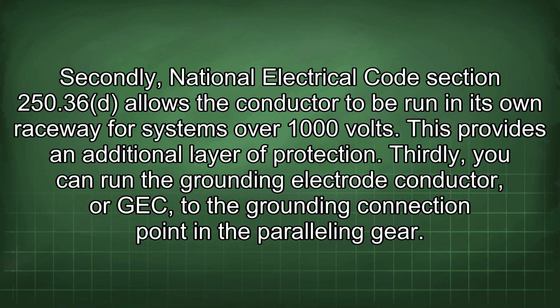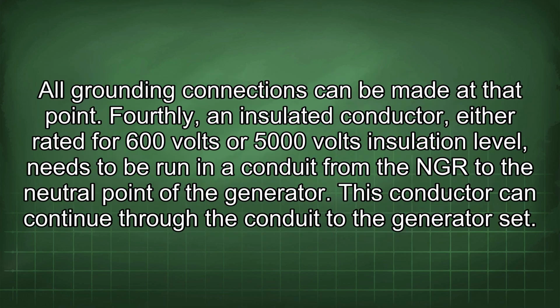Thirdly, you can run the grounding electrode conductor, or GEC, to the grounding connection point in the paralleling gear. All grounding connections can be made at that point. Fourthly, an insulated conductor, either rated for 600 volts or 5000 volts insulation level, needs to be run in a conduit from the NGR to the neutral point of the generator. This conductor can continue through the conduit to the generator set.